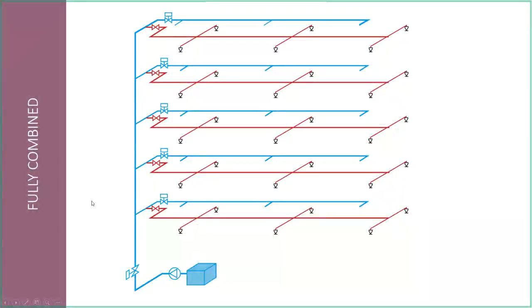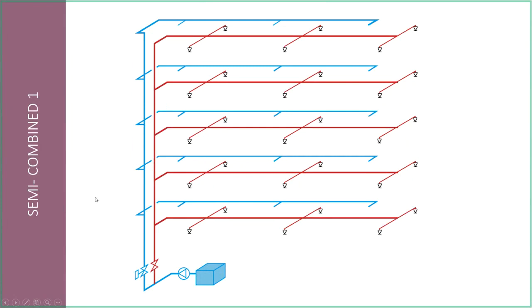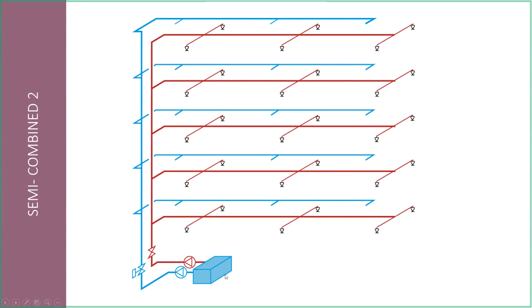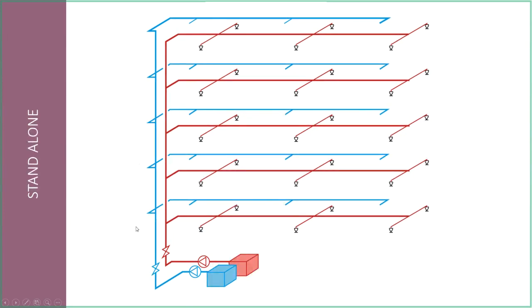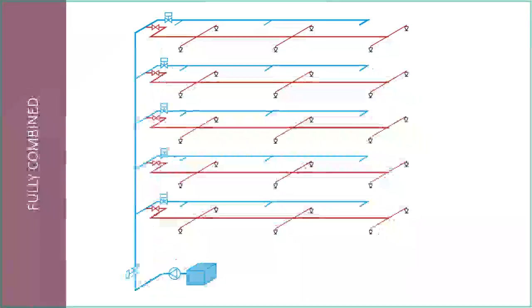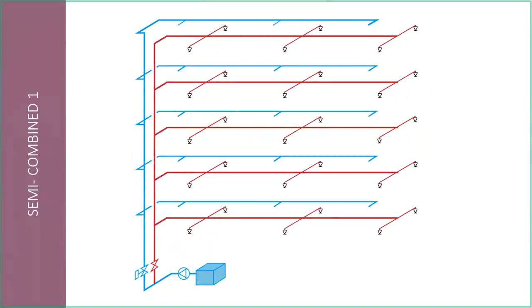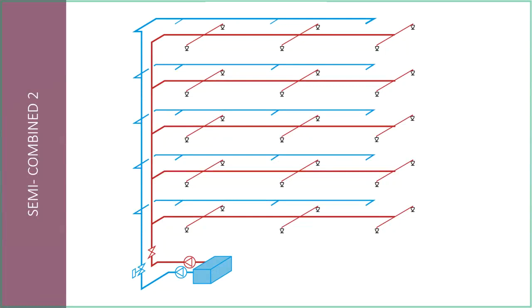A few diagrams showing shared water supply options. A fully combined system: shared tank, shared pump, shared riser, branching off at each floor for sprinklers. Semi-combined option one: shared tank, shared pump, separate riser for sprinklers. Semi-combined option two: shared tank, separate pump, separate riser. And a standalone system: completely separate tank, pump, and riser. Each has its pros and cons, and we can talk about those in more detail in a future episode.